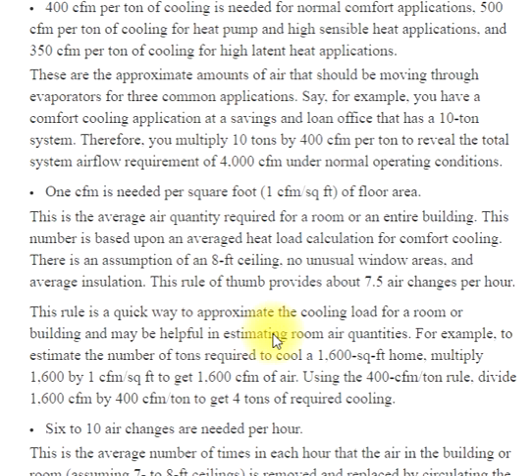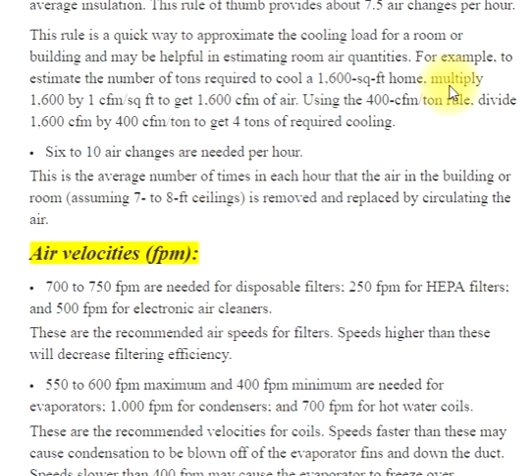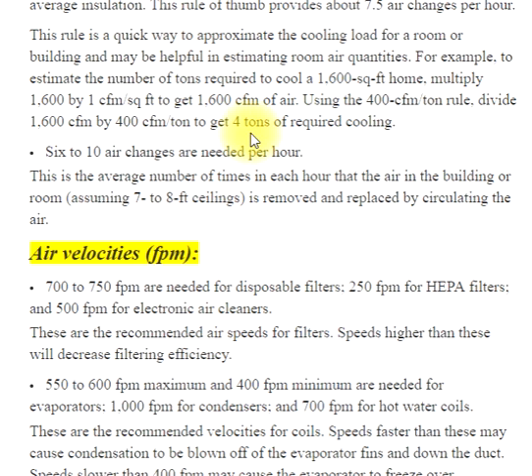For example, to estimate the number of tons required to cool a 1,600 square foot home, multiply 1,600 by 1 CFM per square foot to get 1,600 CFM of air. Using the 400 CFM per ton rule, divide 1,600 CFM by 400 CFM per ton to get 4 tons of required cooling.